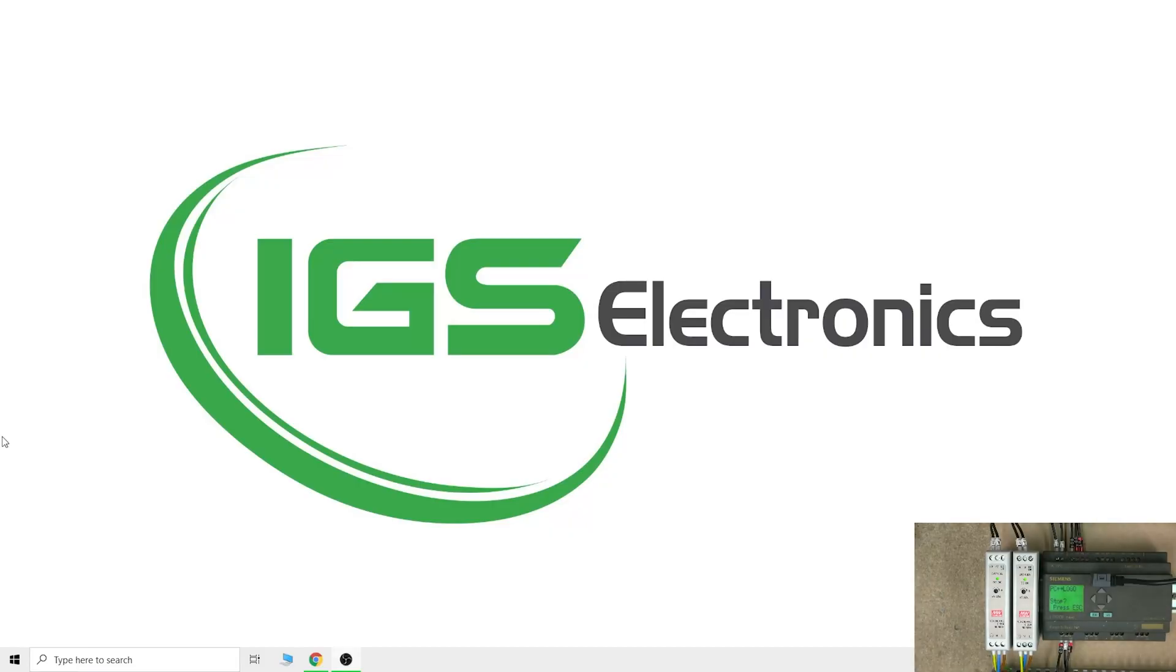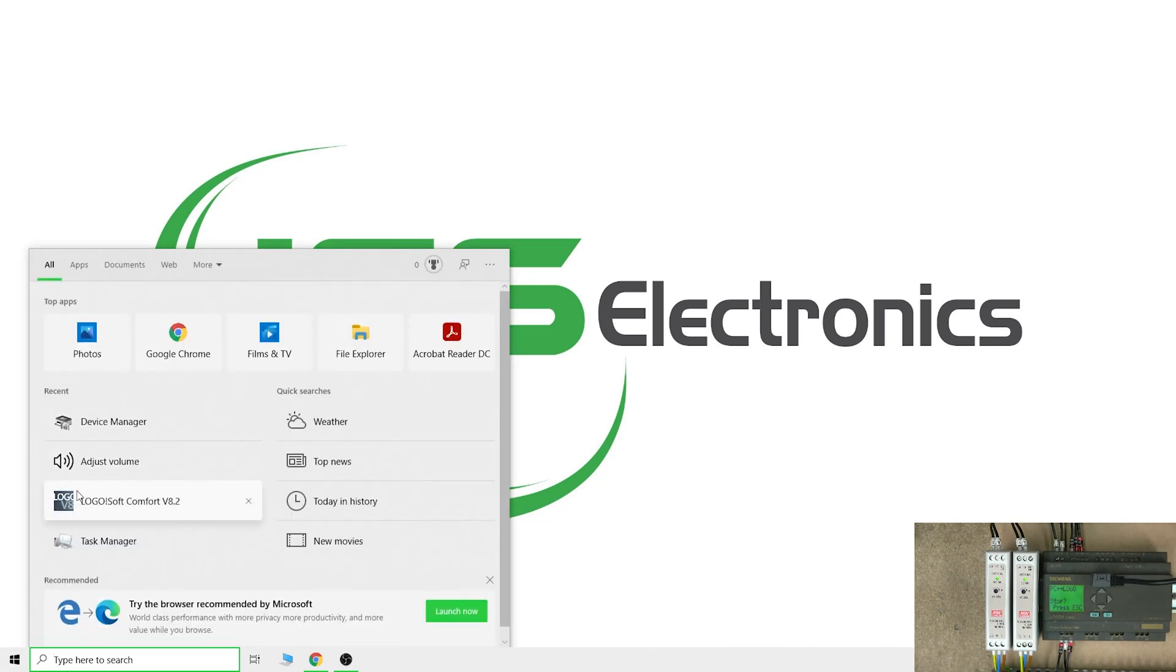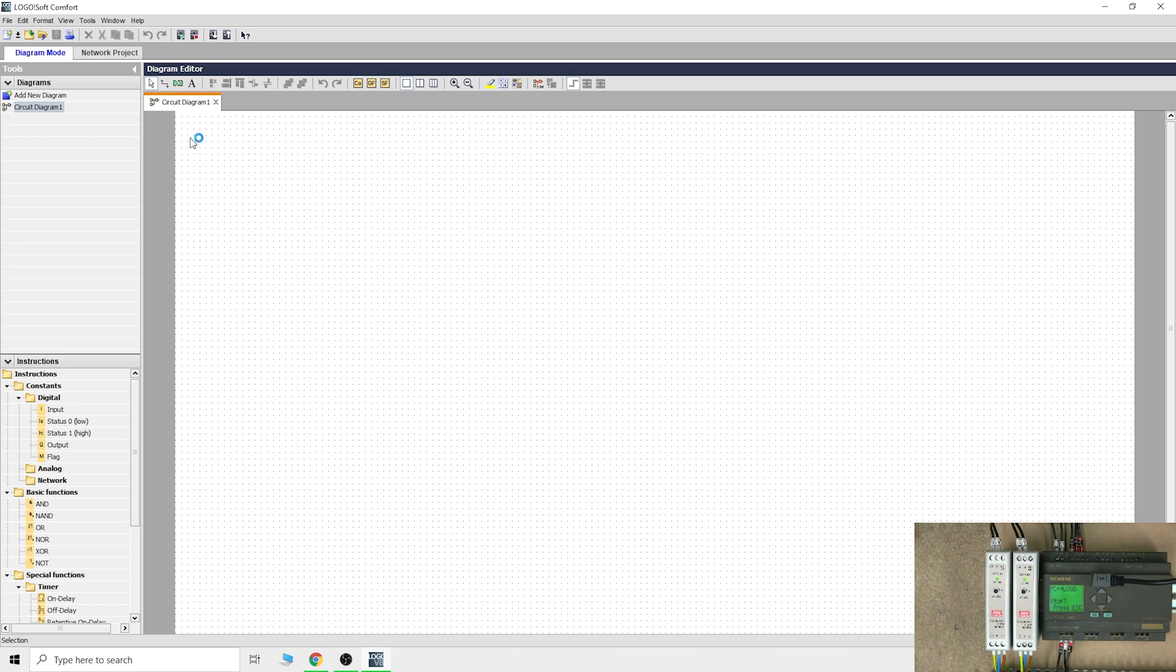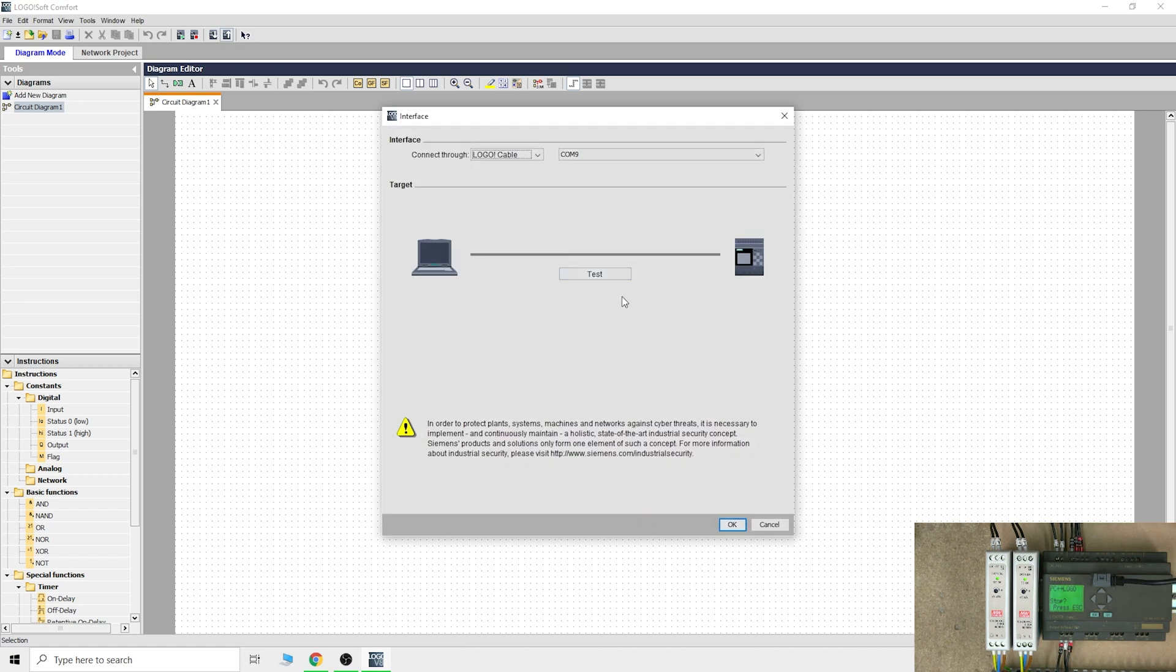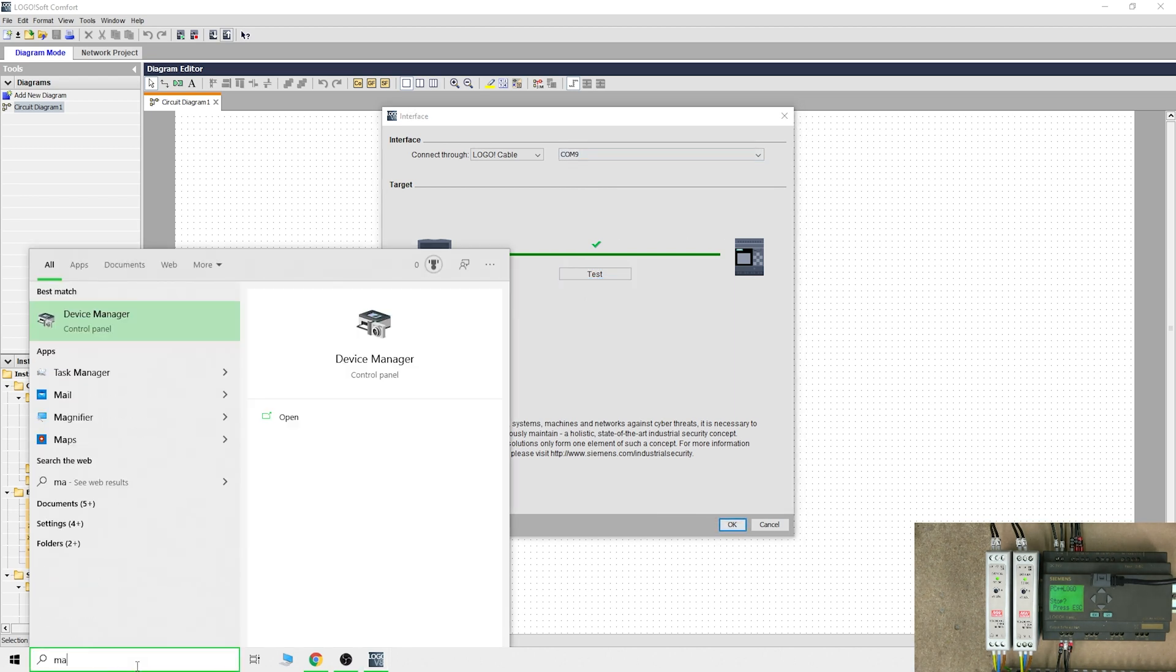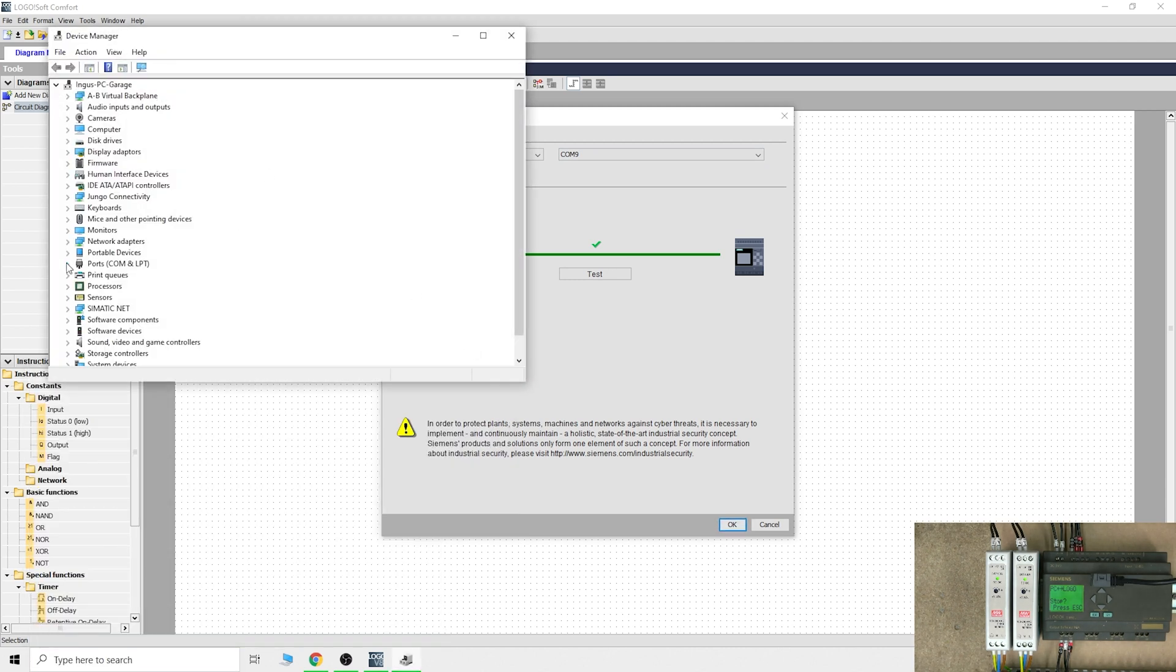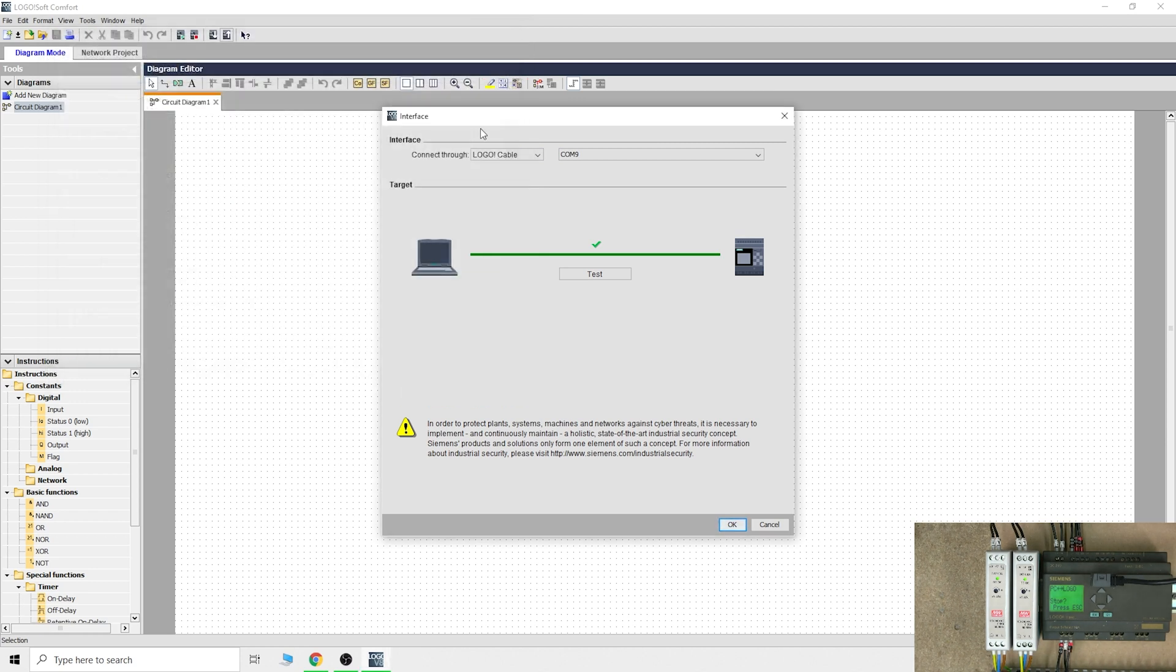Here we are in front of the computer. The program we're going to be loading is LogoSoft Comfort v8.2. Once we are in the program, you can do one thing straight away - jump straight to loading from the Logo. You can see these two options: Logo to PC and PC to Logo. We want Logo to PC. Let's check out what's inside that controller. Quickly I'll show you where to find out what COM port you're in. As you can see, I'm on COM 9. Go to your device manager under USBs and find out which COM port that connection has been selected. That's mine - COM 9.